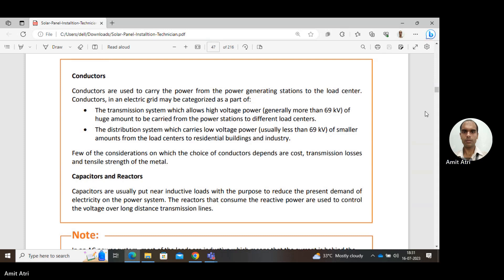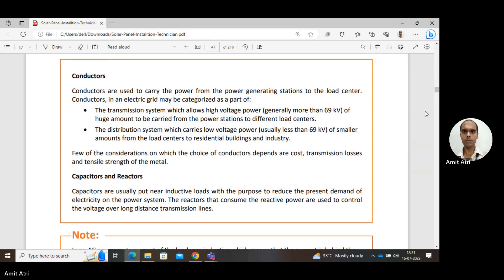In industries, a large number of motors consume huge amounts of power. Since motors are inductive in nature, the overall load becomes inductive. To make the load work at unity power factor, capacitors — which are opposite in nature to inductors — are connected near inductive loads, keeping the overall power factor nearly unity or approximately 0.8 lagging. Conversely, if the load is capacitive, reactors are used.